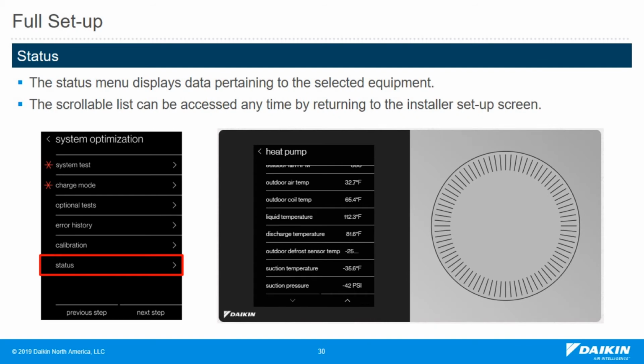On this screen for optimization, we also have status. The status is multiple screens. It allows you to view outdoor air temp, coil temp, heat exchanger temp, indoor coil temp, liquid temp, suction temp, the pressures, the mode, the percentage of operation, the percentage of fan operation, the percentage of dehumidification, the revolutions per second of the compressor, and the outdoor fan. All the information that can be critical to troubleshooting is available to you here. You can calculate the superheat off of this screen.